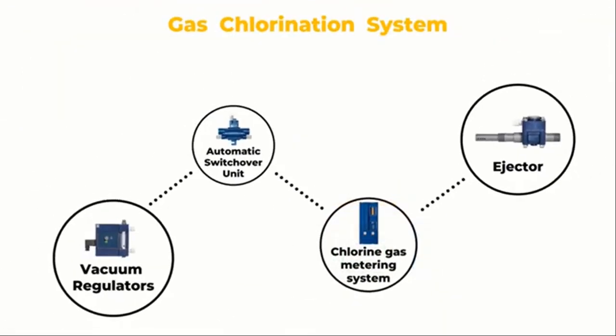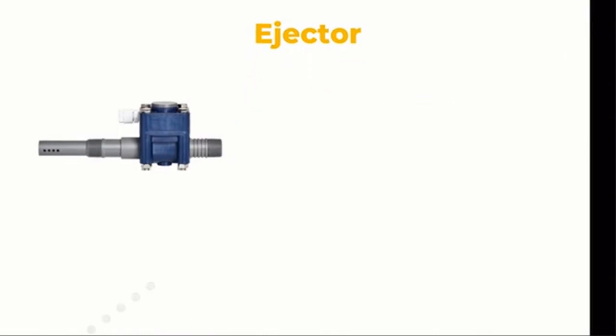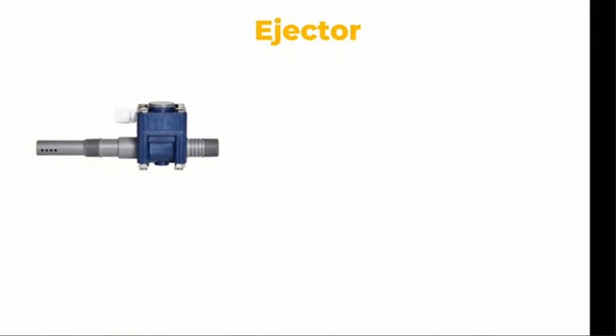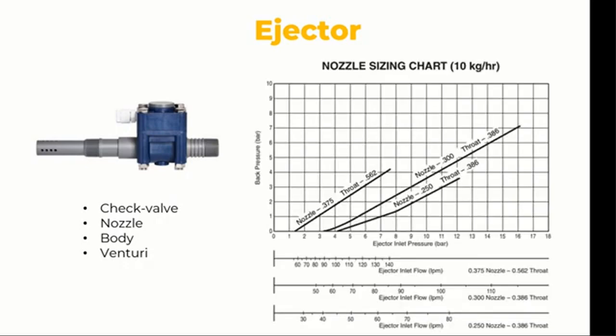The ejector is the final part. It's a mechanical mechanism that controls the system by creating a vacuum and combining chlorine gas and water. It consists of the following components: the venturi, check valve, nozzle, and body. Manufacturers create many different ejectors. To determine the water flow and pressure needs for each ejector, consult the nozzle performance charts and curves found in the manufacturer's instruction manuals. Here is the nozzle ejector curve illustration.